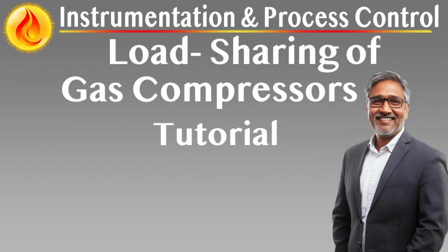PID-based load balancing response. Each load-sharing controller calculates the difference between its selected deviation and the station-wide average. A load balancing PID loop then processes this error to generate a correction signal. This signal is combined with the primary capacity control response, if applicable, to determine the final controller output.